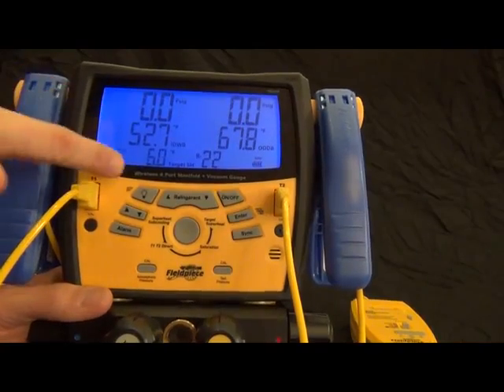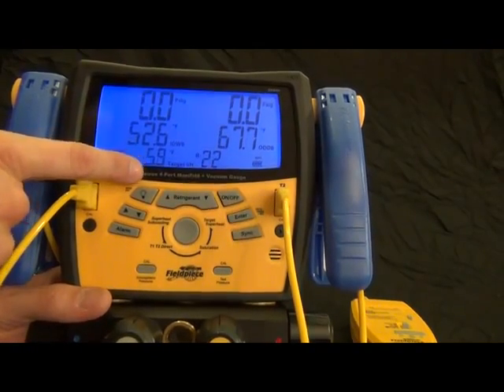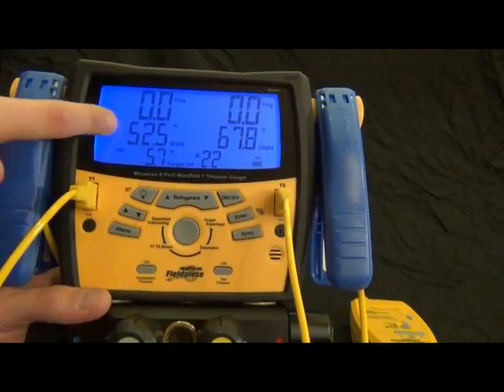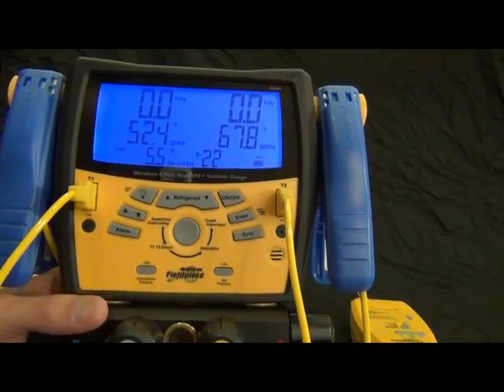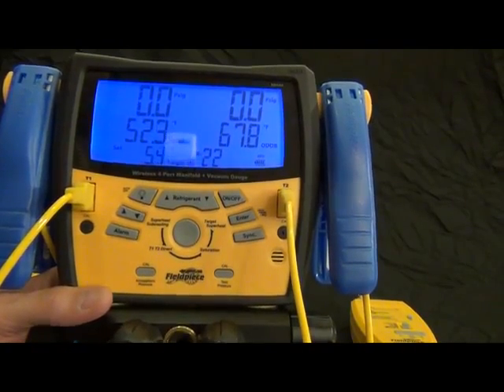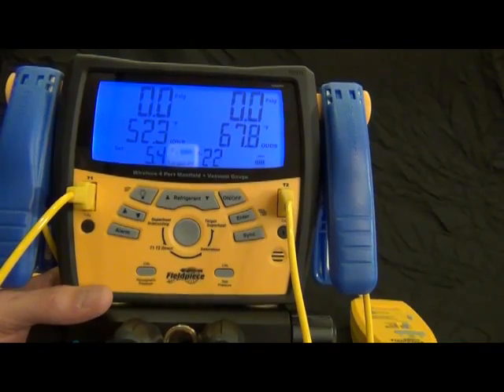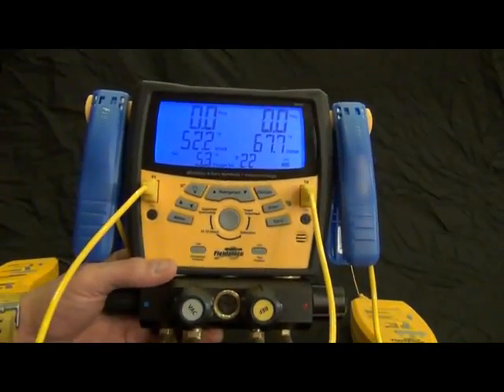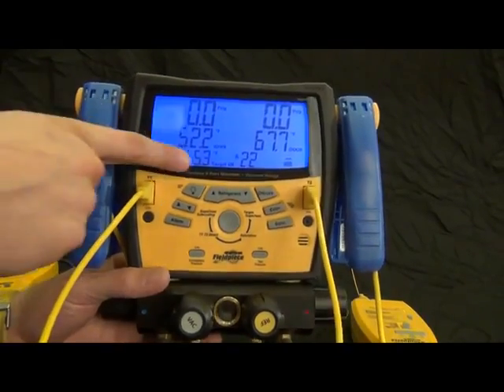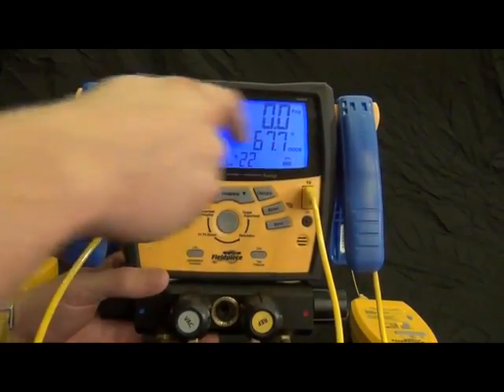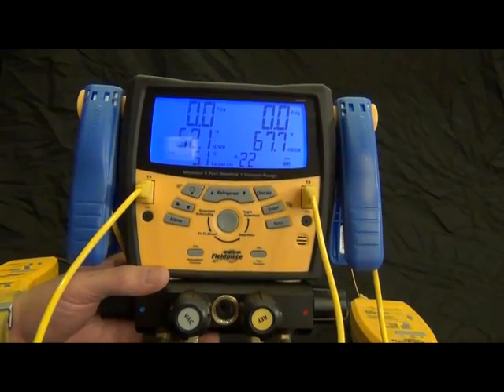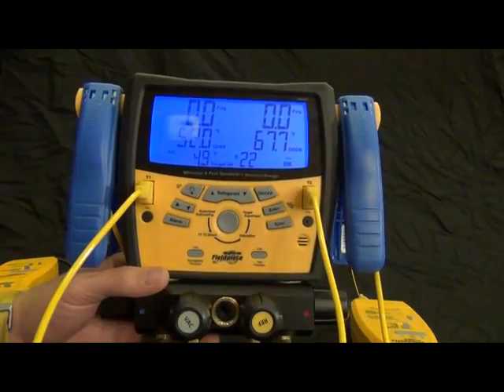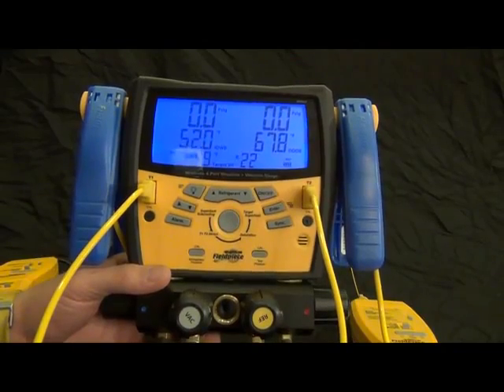So what it's doing is you see this 5.8 target superheat. It's literally taking the wet bulb measurement and the outdoor dry bulb measurement and looking up on a psychrometric chart that's built in to the S-Man 4 and calculating your live target superheat. So now I can just actually go ahead and set this up to a system, walk outside, hook up all my hoses and my clamps, and get my live measurement, temperature measurements while looking at my pressures and my suction line and liquid line temperatures. So that's the wireless feature of the S-Man 4.